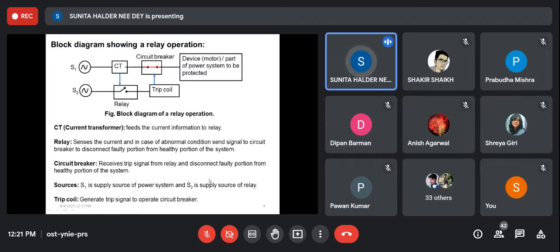So what will be the basic block diagram of a relaying operation? Actually, this S1 is the system. The system is entrusted to supply some device, maybe a motor or a part of a power system. But to protect that system, there must be a CT to give the information about the current to the relay. There must be a circuit breaker in series with the system connection, so that it will be closed under healthy condition and it will be opened under unhealthy condition.